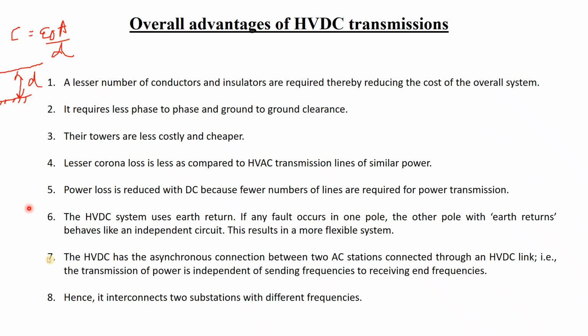Also, if the ground clearance is not sufficient, then since the dielectric strength of the air is limited, the electric stress, or potential gradient, will increase. This may result in a dielectric breakdown, and a flashover may take place. So there is some prescribed ground clearance required.